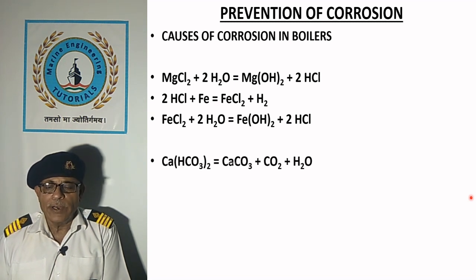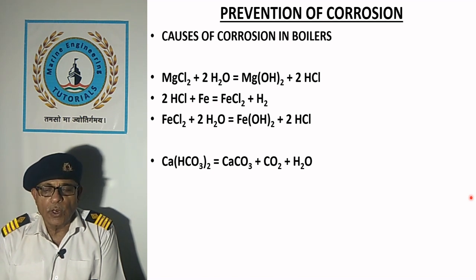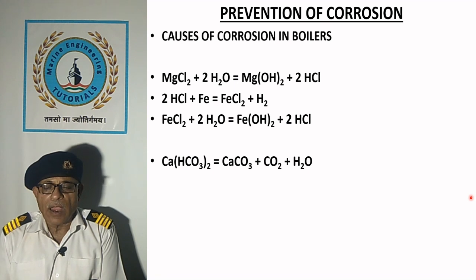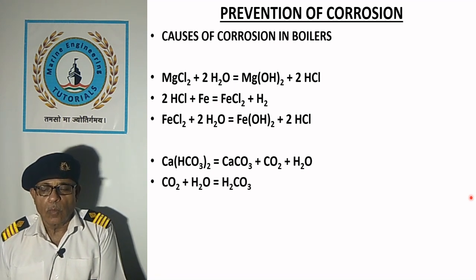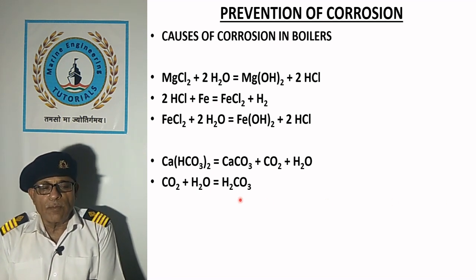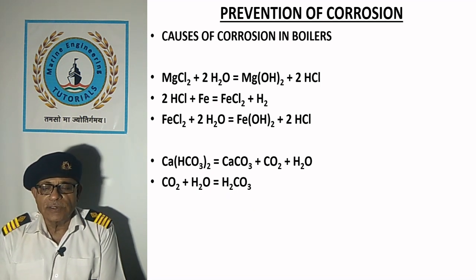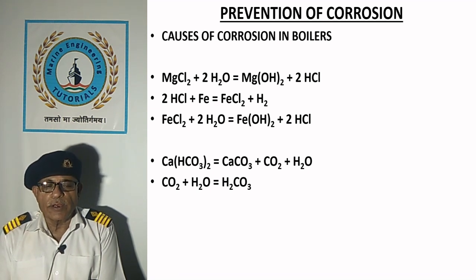On heating, calcium bicarbonate is decomposed into calcium carbonate, carbon dioxide and water. Carbon dioxide and water recombine to form carbonic acid, which causes acidity in the water. Carbon dioxide is eliminated by addition of amines in boiler water.